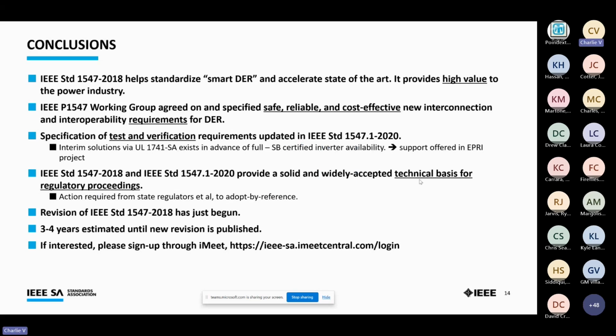In implementing the UL 1741 SB testing, areas of new material may be entered related to security and possibly energy storage, and we'll hit those. But in the interim, there aren't going to be massive changes that diminish things. If you want to reference SA or SB now, of course this is my opinion, I'm not seeing anything on the revision that's going to completely rewrite the rules from a performance viewpoint.